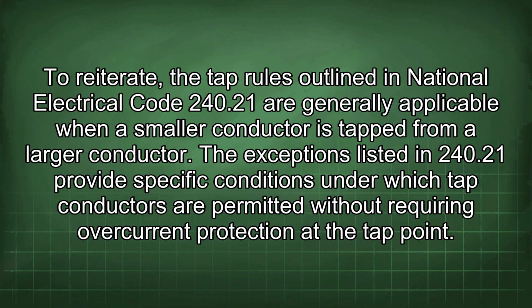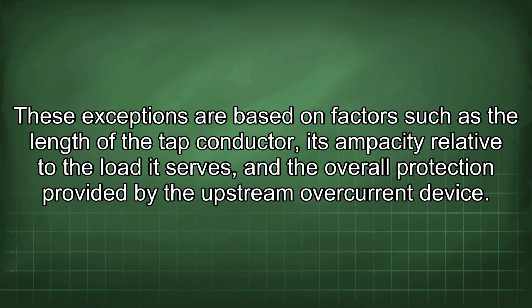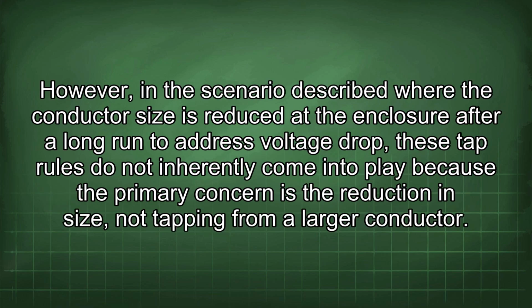To reiterate, the tap rules outlined in National Electrical Code 240.21 are generally applicable when a smaller conductor is tapped from a larger conductor. The exceptions listed in 240.21 provide specific conditions under which tap conductors are permitted without requiring overcurrent protection at the tap point. These exceptions are based on factors such as the length of the tap conductor, its ampacity relative to the load it serves, and the overall protection provided by the upstream overcurrent device. However, in the scenario described, where the conductor size is reduced at the enclosure after a long run to address voltage drop, these tap rules do not inherently come into play because the primary concern is the reduction in size, not tapping from a larger conductor.